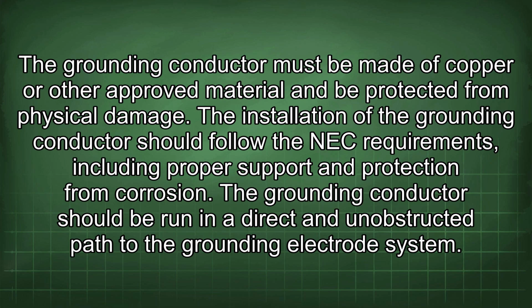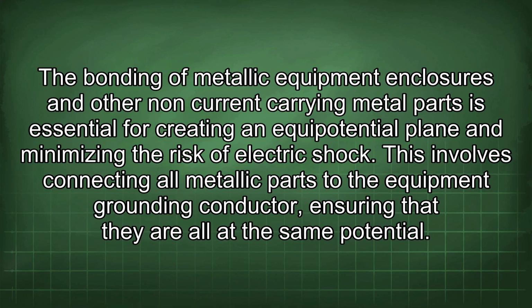The installation of the grounding conductor should follow the NEC requirements, including proper support and protection from corrosion. The grounding conductor should be run in a direct and unobstructed path to the grounding electrode system. The bonding of metallic equipment enclosures and other non-current carrying metal parts is essential for creating an equipotential plane and minimizing the risk of electric shock.